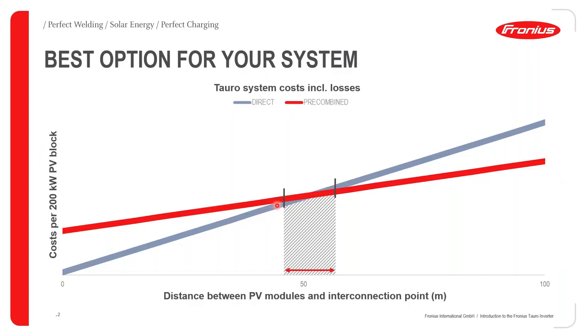This is the inverter version whereby the string cables are connected directly to the inverter. As we can see, for the same distances from, let's say, 0 to 50 meters, the cost of the pre-combined version, whereby you go into the inverter with a maximum of 6 DC connections, will be slightly higher when the distance is much shorter. On the flip side, once the distance exceeds 50 meters, the direct version starts losing the gains that you saw when the distance was not as long, and the opposite happens: the pre-combined version starts to gain a lot of advantage over the direct version of the inverter.